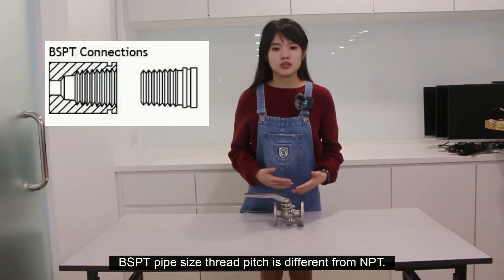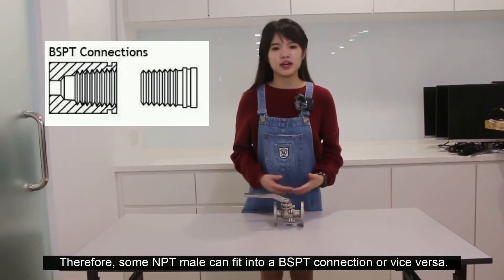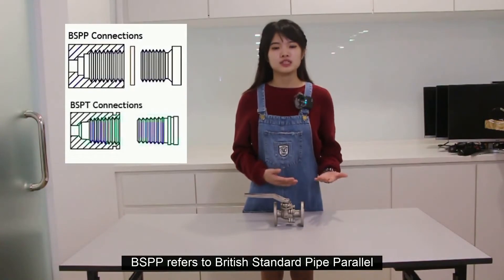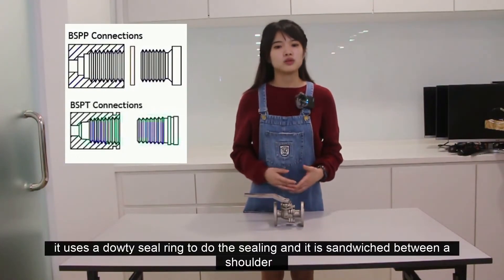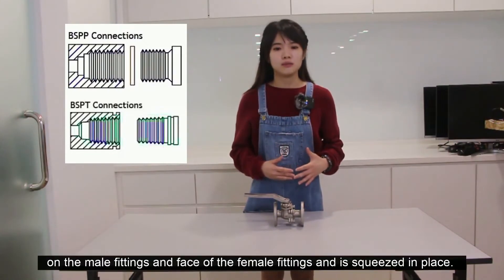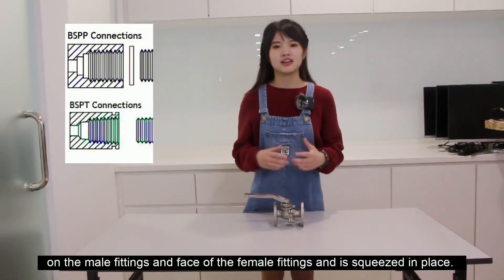BSPT pipe size thread pitch is different from NPT. Therefore, some NPT male fittings can fit into a BSPT connection, or vice versa. BSPP refers to British Standard Pipe Parallel. It uses a dowty seal ring to do the sealing, which is sandwiched between a shoulder on the male fitting and the face of the female fitting, and is squeezed in place.